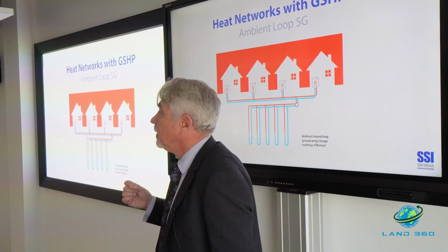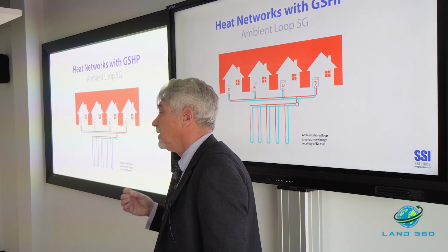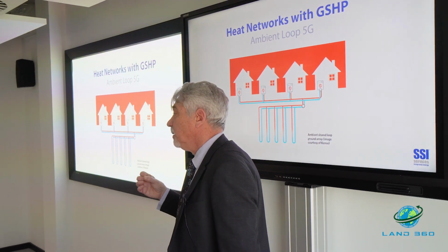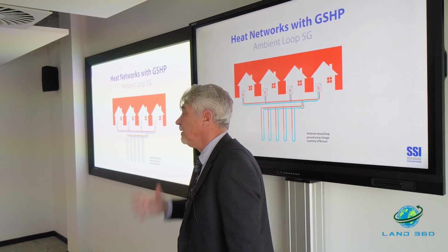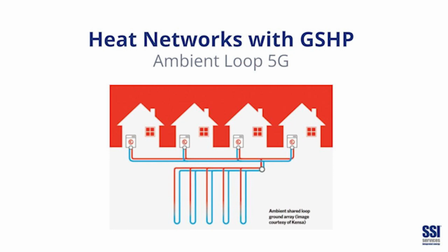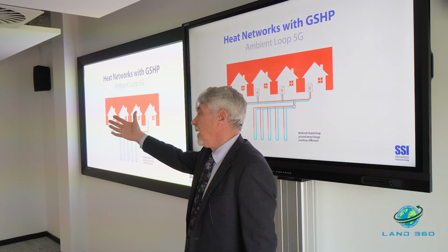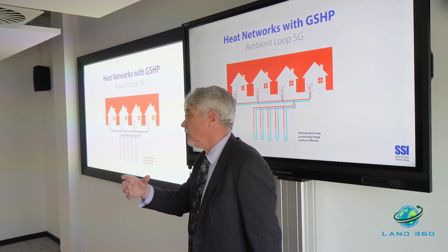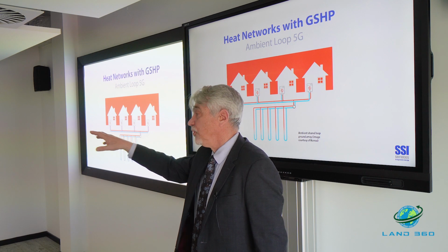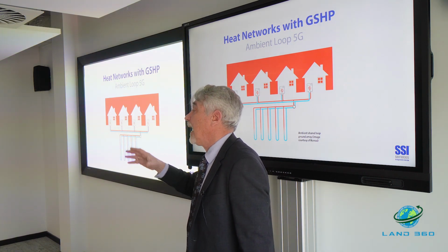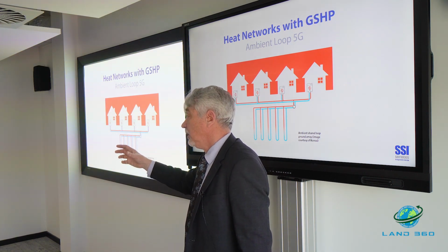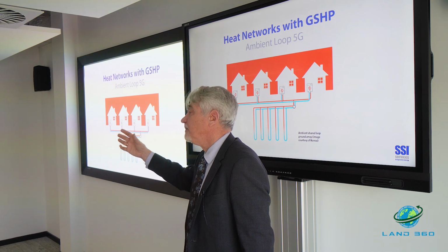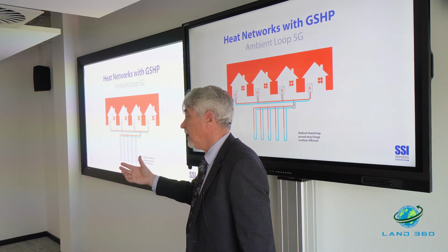With an ambient loop, we take the energy out of the ground, and instead of turning that into high temperature and delivering it to the properties, we deliver that ambient energy to the property and put a heat pump in each individual property. So if you've got an estate with bungalows, a big care home, and perhaps some commercial buildings, we can deliver that ambient temperature to each, and they can have the appropriate ground source or water source heat pump fitted to provide that energy.